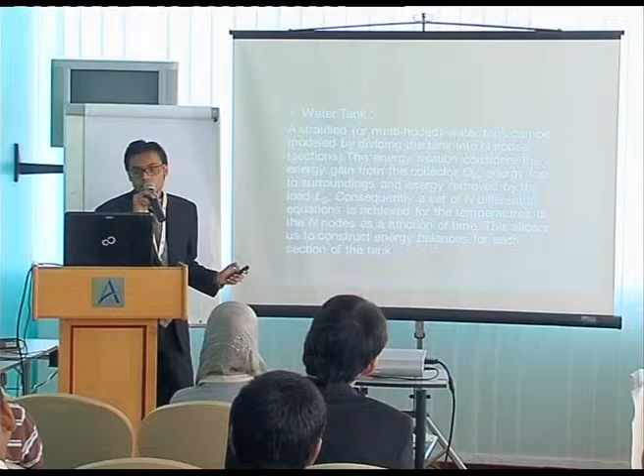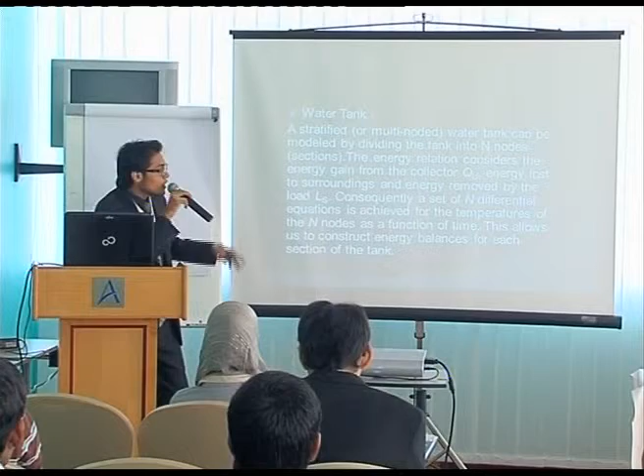Now in the water tank, if you consider QU as the heat gain from the collector and LS as the load, the cooling load, or you can say the energy removed, you can formulate n differential equations. If there are n nodes, as we considered in our storage tanks, there were 3 or 4 in the stratified one, so we can make n differential equations in order to determine the energy balance equation for each section of the tank. So we had 3 or 4 sections, which will give the energy balance relation at any point in the storage tank.